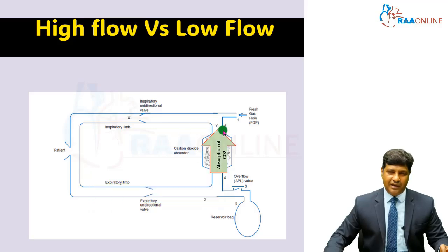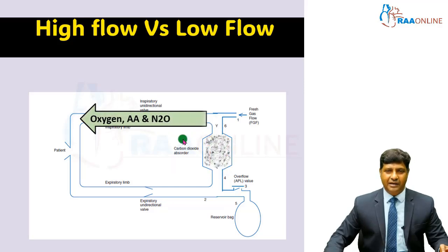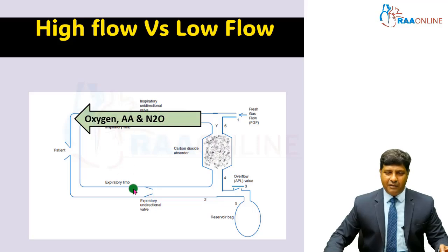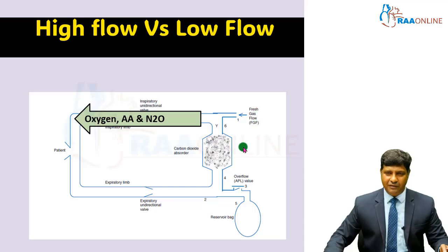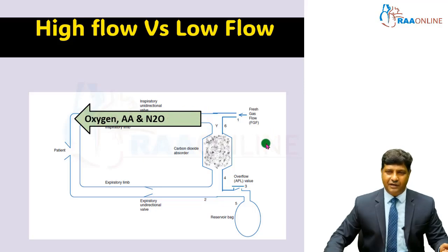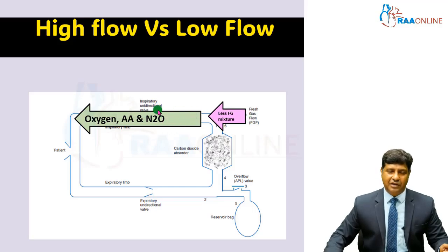After the carbon dioxide is absorbed, the gas reaches back to the inspiratory limb. This gas coming from the expiratory limb through the circle absorber or canister has different characteristics than the gas coming from the fresh gas flow. The volume of the exhaled gases is much higher compared to the fresh gas flow, since the exhaled gas forms the major component and what we need to supply is much less.